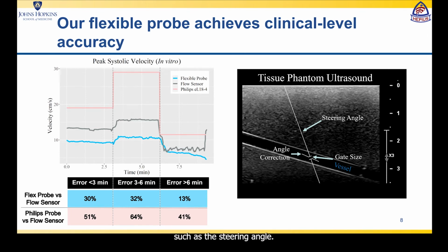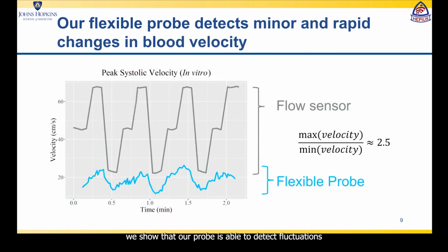Next, we show that our probe is able to detect fluctuations in blood velocity that happen over short periods of time. As with many cardiac devices, we care most about the degree of fluctuation. Although the exact velocity values may be different here, we have already shown that we fall within clinically accepted error bounds, and as you can see, the ratio of maximum to minimum velocities detected is approximately equal for the ground truth and our flexible probe.